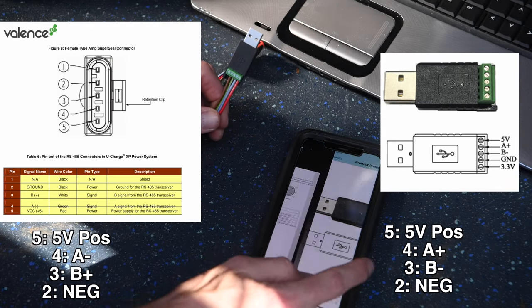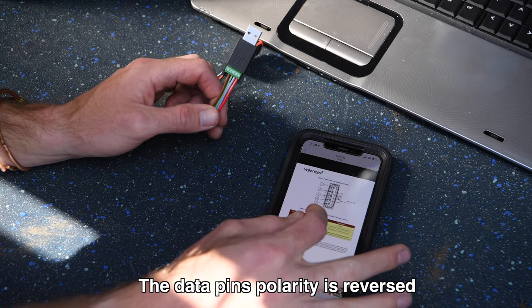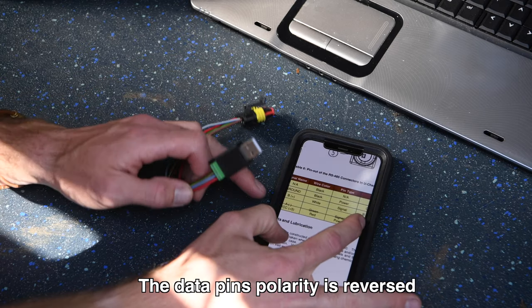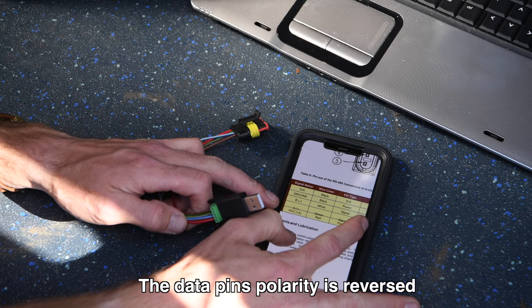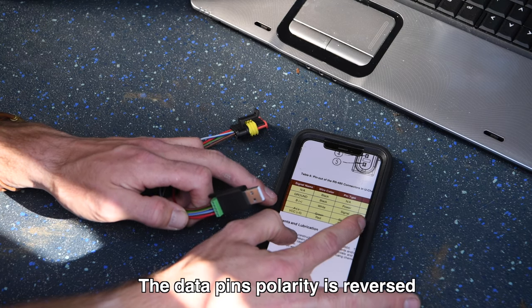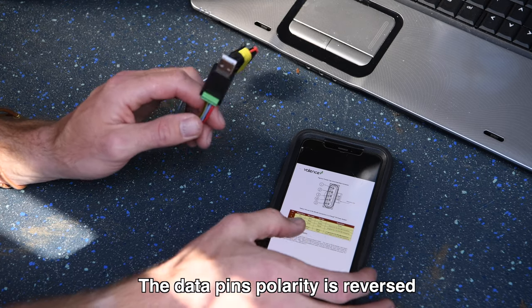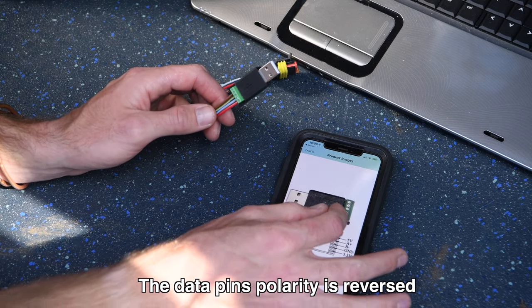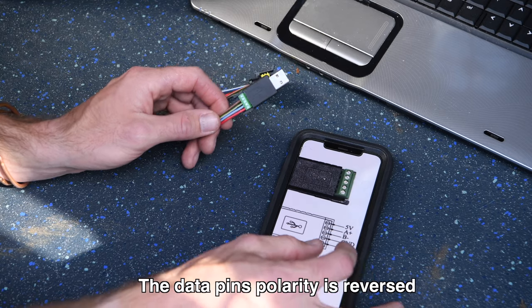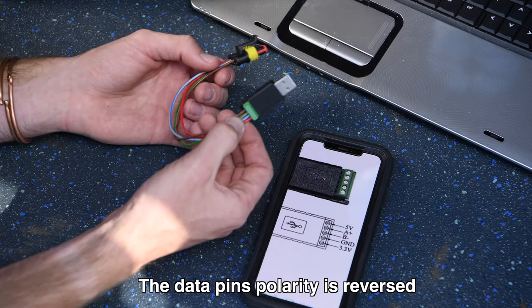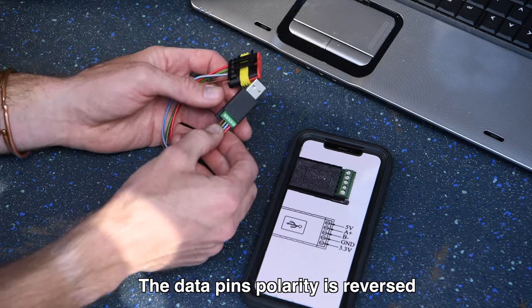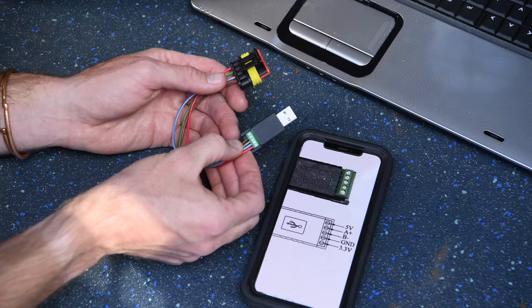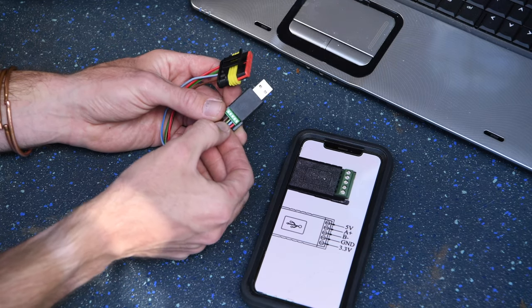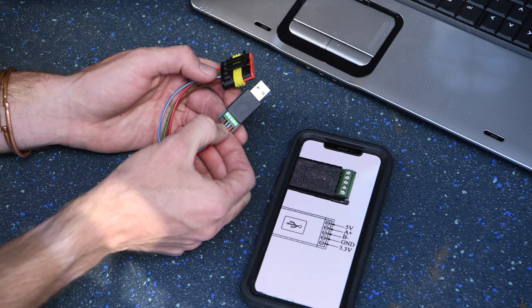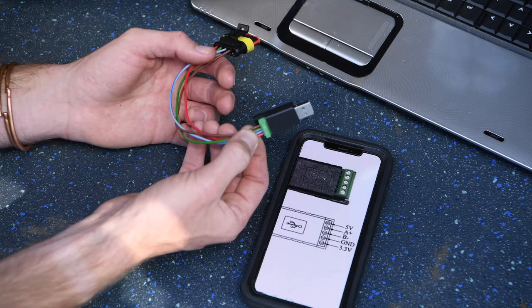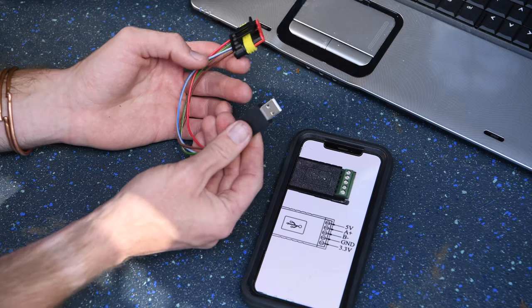What I didn't read is there's a slight formatting error in this manual, which puts the little minus mark next to the A, which is A minus, B plus on the data, whilst on this one it labels them as A plus, B minus. So I was doing A to A, B to B, but actually in this case it was the other way around. It was an A minus. So once I swapped my A plus, my A minus, my B plus the other way around, or switched the data pins, it worked first time.